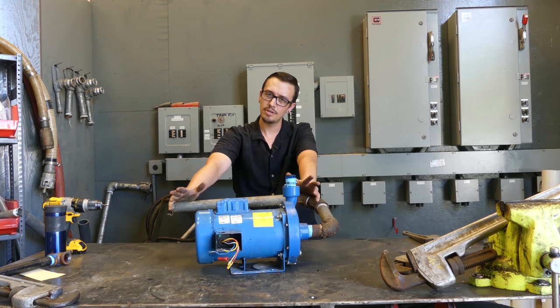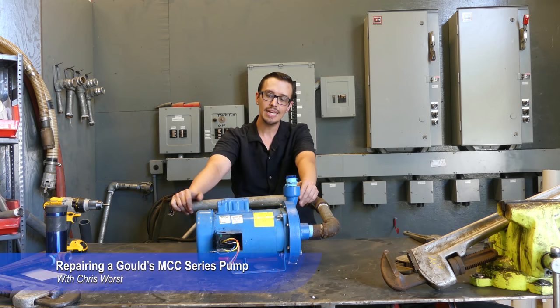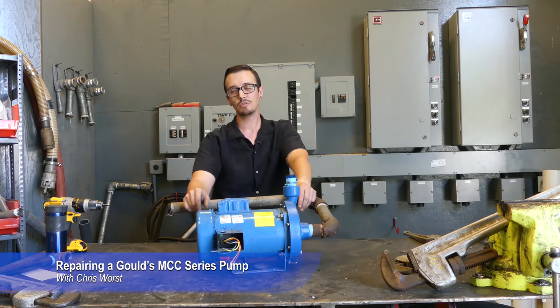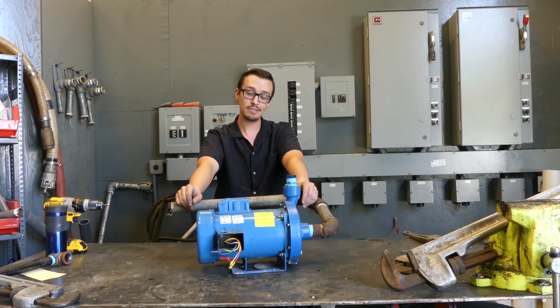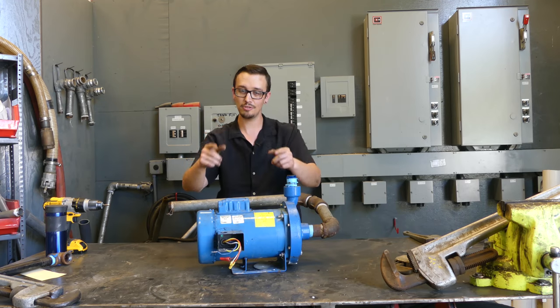Hey, welcome back to another video. Chris with RC Wurst here. Today we've got a Goulds pump that's used for circulation — just an end-suction type basic pump. What we're going to be doing is the customer reported that the pump was leaking around the volute. We ordered a new seal because we felt like that was most likely the situation, so we're going to replace that seal, put it back together, and test it to see if that solved the problem.